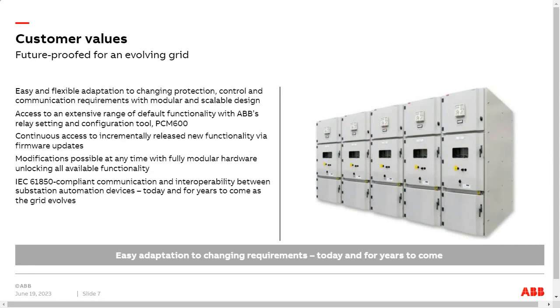Future-proof. It's quite easy to change protection, control and communication functions of the device just by using the PCM600 tool. And then, as we already mentioned, there is continuous access to incrementally released new functionality via firmware updates. For example, now when we come with this 1.1 firmware, you can update a device having the 1.0 firmware to get, for example, the motor protection functionality or even the arc protection functionality. And this can happen directly, before even commissioning the system, or later on down the line, a couple of years afterwards.